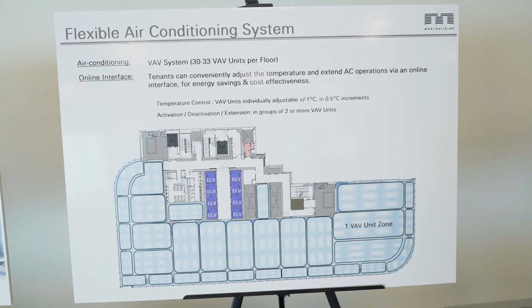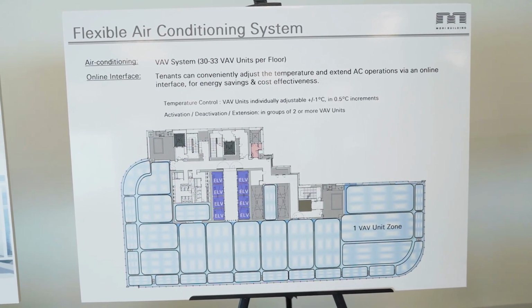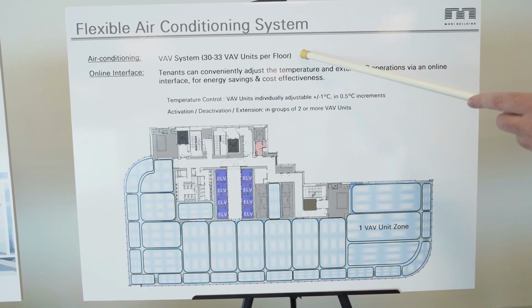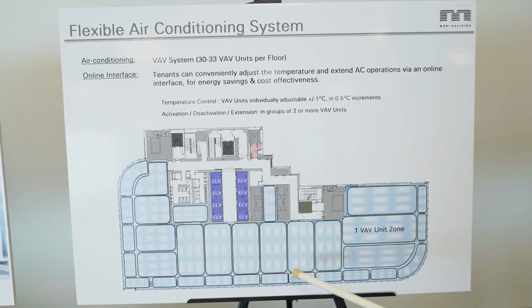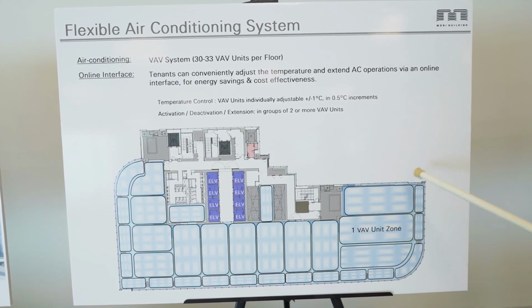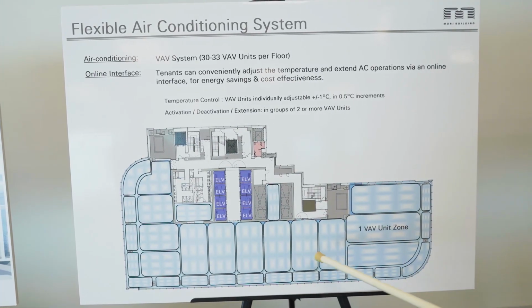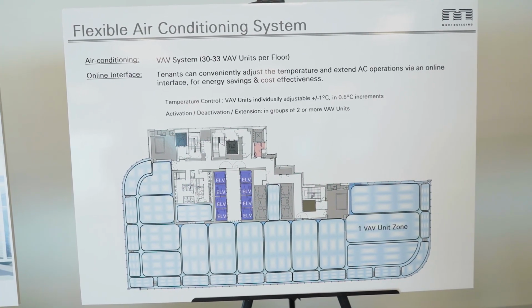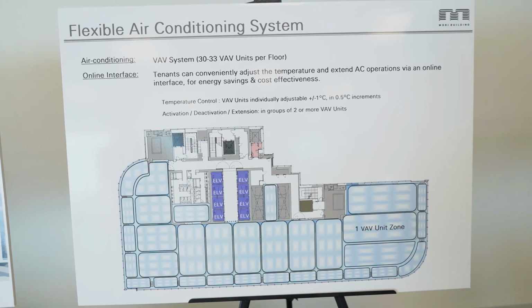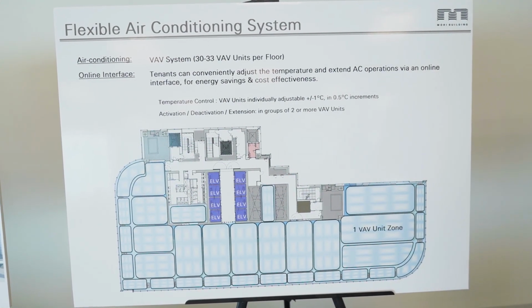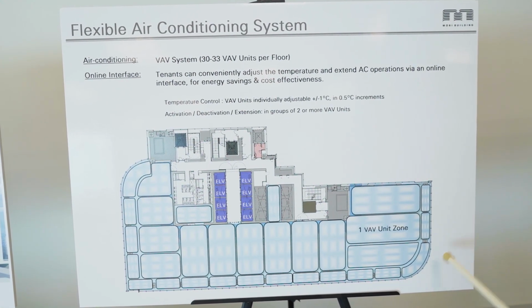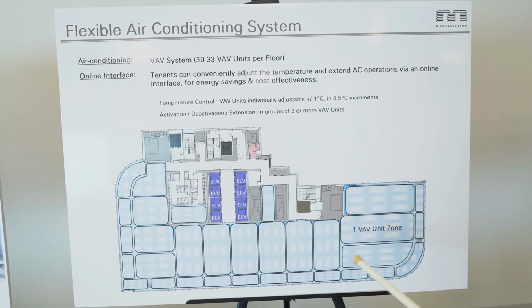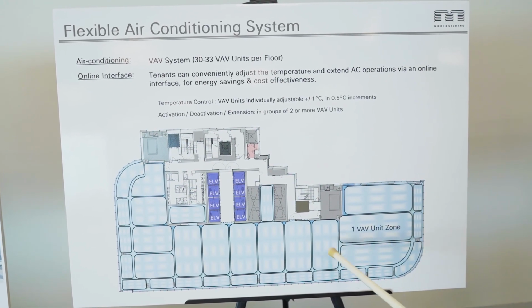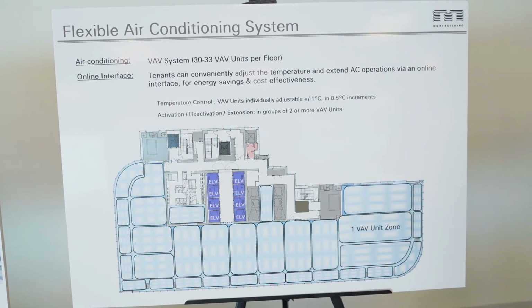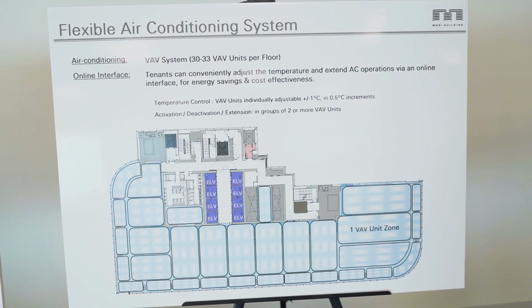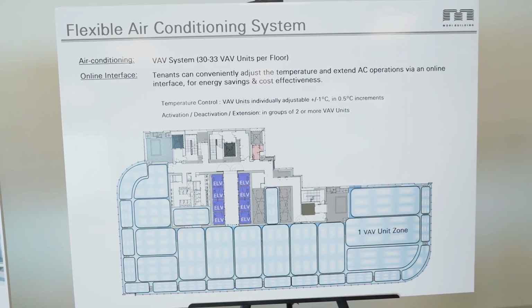As mentioned, Jakarta MORI Tower will feature a very unique and flexible air conditioning system. Each floor plate will have between 30 and 33 individual VAV zones. With these zones, tenants can control the operation of the AC system within each zone individually. So especially for tenants who have divisions coming in early or working late, rather than turning on a half floor plate or full floor plate for their AC service, it is possible to control individual zones quite minutely, so quite efficient, and a very good energy and cost saving measure.